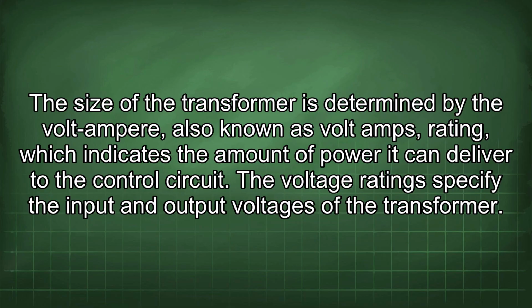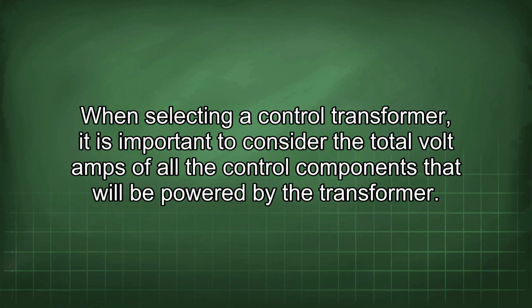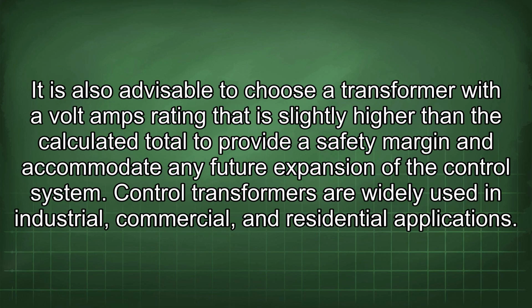The size of the transformer is determined by the volt-ampere, also known as voltamps, rating, which indicates the amount of power it can deliver to the control circuit. The voltage ratings specify the input and output voltages of the transformer. When selecting a control transformer, it is important to consider the total volt-amps of all the control components that will be powered by the transformer. It is also advisable to choose a transformer with a volt-amps rating that is slightly higher than the calculated total to provide a safety margin and accommodate any future expansion of the control system.